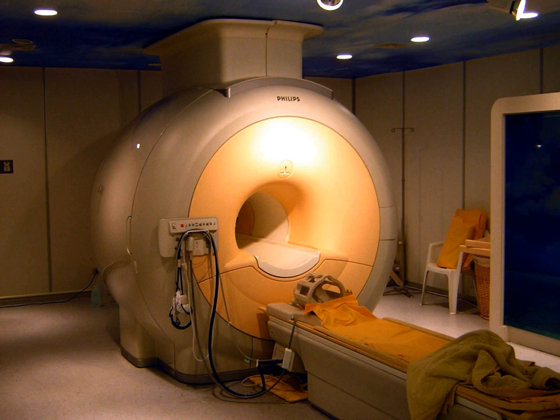Since the additional field is a gradient, it has units of Gauss per centimeter or millitesla per meter, mT per meter. High-performance gradient coils used in MRI are typically capable of producing a gradient magnetic field of approximately 30 mT per meter or higher for a 1.5 T MRI.